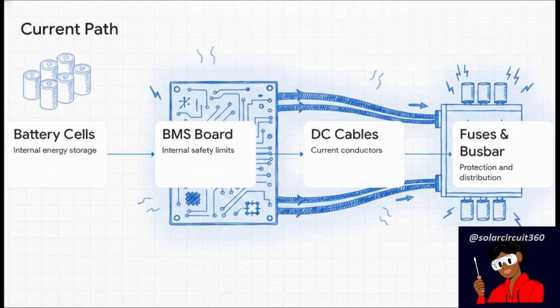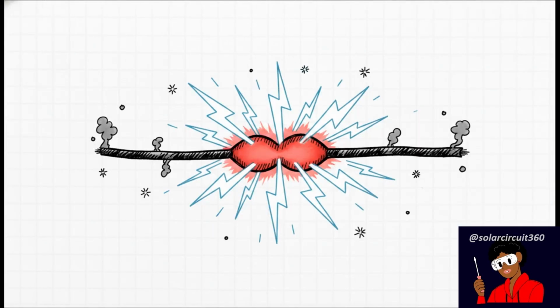Every single component in this chain has to be rated to safely carry that immense current. If your cables are even slightly undersized for a 200+ amp load, the electrical resistance will literally turn them into dangerous heating elements. The physics here are totally unforgiving. Voltage drop equals current multiplied by resistance. Higher current means more energy lost as heat and significantly lower efficiency. A cable might physically fit perfectly into the back of your inverter, but if it's electrically undersized, you aren't just losing power. You are looking at a severe fire hazard.